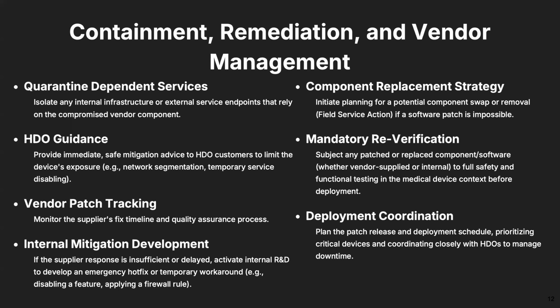There have been instances where we have heard of device makers telling a hospital to simply turn off the Bluetooth or isolate it on a network or stop using some component or facet of the clinical operation. There's a variety of ways that remediation can occur. Some can severely impact clinical care delivery, and some the patient or the provider won't even notice, right? So really ensuring that you have a strategy in place for the vulnerability is important. And again, this is one of those moments where security could butt heads with the business priority, and you want to work through that in a way that everybody comes out happy.